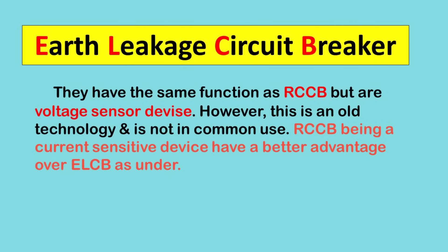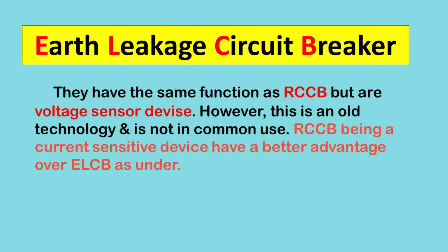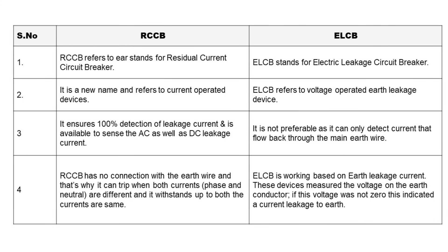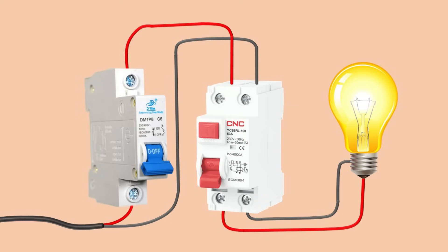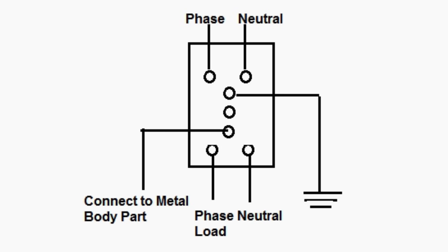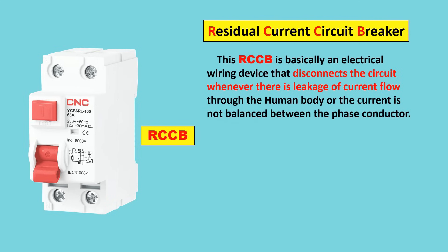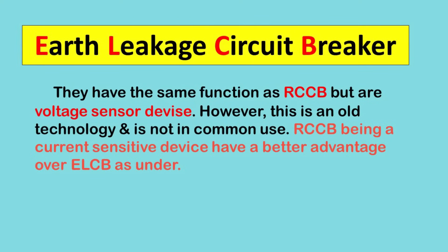Next device is ELCB. Full form of ELCB is Earth Leakage Circuit Breaker. Its working is the same as RCCB — to protect you from electrical shocks. The difference is: RCCB operates on current and requires only phase and neutral supply for connection, while ELCB operates on voltage and requires phase supply, neutral supply, and an earthing wire. Both RCCB and ELCB provide protection from electric shocks and earth fault.